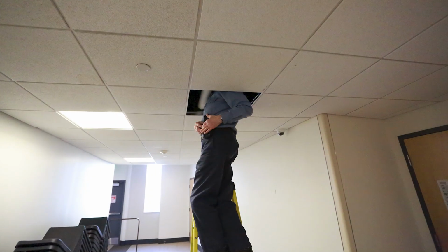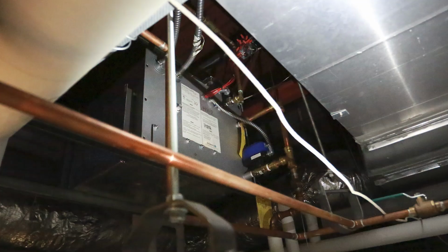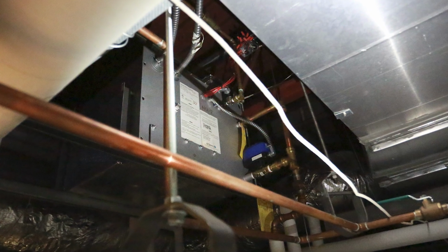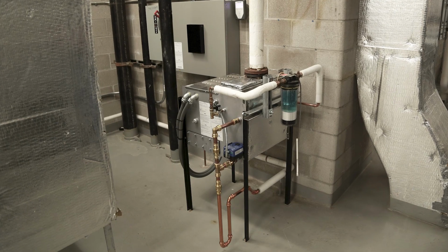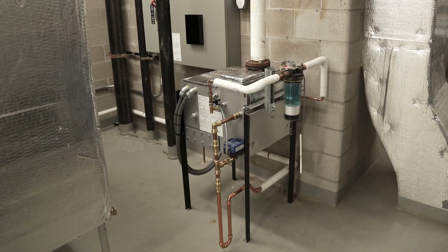Sure. And so that placement of, well, where can I put it? The other thing to keep in mind is if you put it tucked away in a corner or up in a ceiling, I often think of if it's out of mind, it's not likely to be maintained. So if it's in a mechanical room where you've got a lot of other equipment you're going to service, you're going to know, hey, that thing may need some work. And you can check on it. So you have to think through that portion as well. If you have to make the steam, make it accessible because there will be some maintenance.